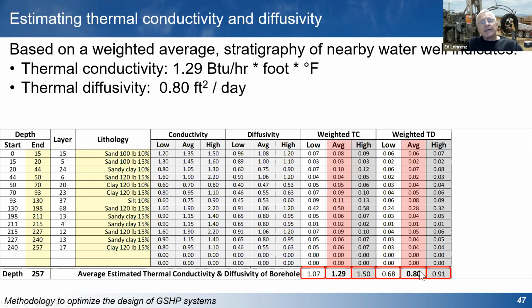Thermal diffusivity worked out to roughly an average of about 0.8 square feet per day. So the initial modeling was based on what we could find without drilling a test borehole, or spending $5,000 or $10,000 or $15,000 drilling a test borehole and running a thermal conductivity test. So we try and avoid that expense right up front by getting as good an estimate as we could, either by looking at water well databases or by talking to drilling contractors or whatever.